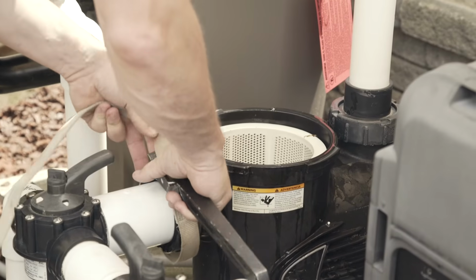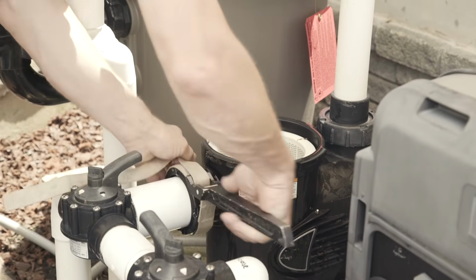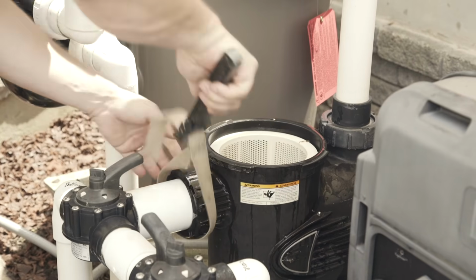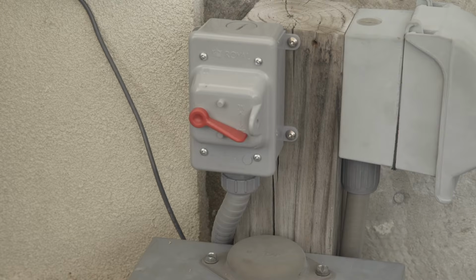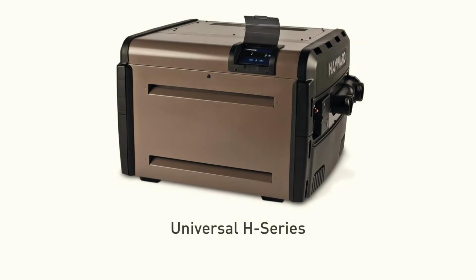For this installation, we will be removing an existing single-speed pump that is connected to a time clock. There is one incandescent light wired to an outside switch that resides in a single gang box. The heater is a Hayward Universal H-Series heater set for standalone operation. The heater is not hooked up to an external controller.